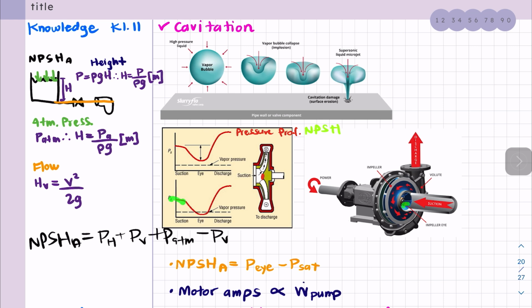The pressure on my suction is going to be different than the pressure on the eye, and way different than the pressure on my discharge. That's important because it helps us pick the right pump for our system, and that's what helps us prevent cavitation. If we select the pump appropriate for the application with sufficient net positive suction head value, it helps prevent cavitation and ensures the fluid flows with no issues for our pump.